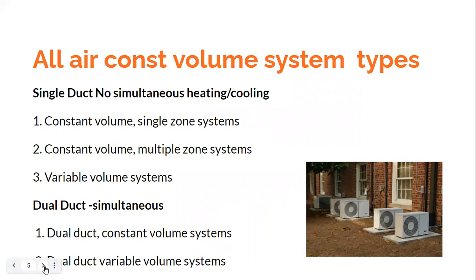If you want to classify it further, then this is one way of classifying it. As I said, we can club the all air systems into constant volume systems and variable volume systems. Again, in constant volume systems, you would have further classification as mentioned over here. This could be a single duct system, meaning that in the duct, either you supply the hot air or the cool air. You don't have a simultaneous heating or cooling operation. Because you have a single duct, obviously you need to supply either the cool air or hot air, but there is no simultaneous possibility of heating and cooling. So you have a single supply duct and a single return duct. That is called a single duct system.